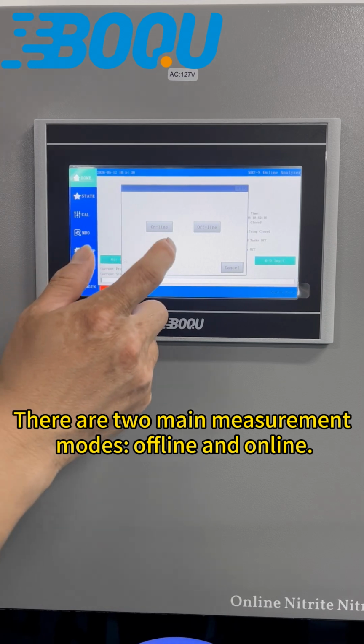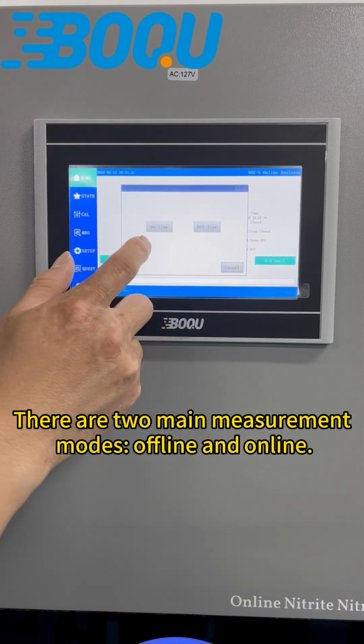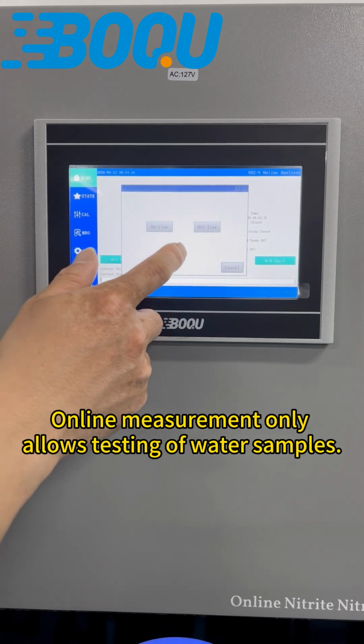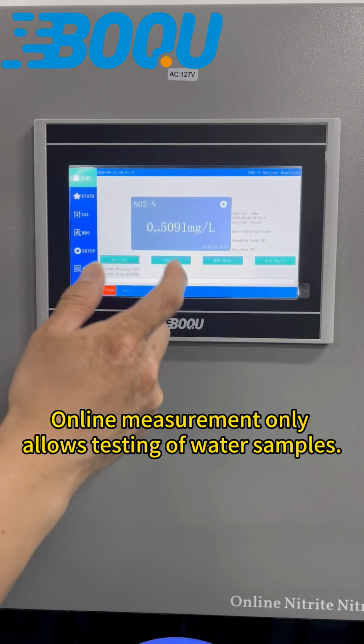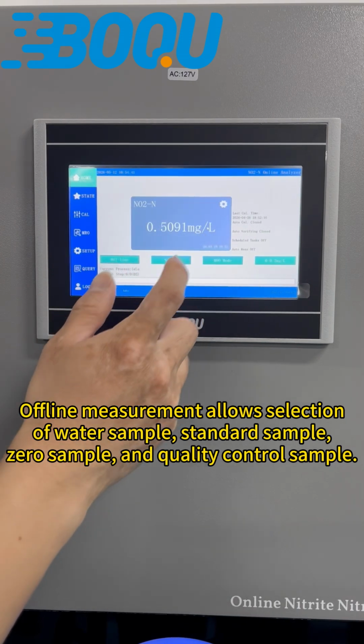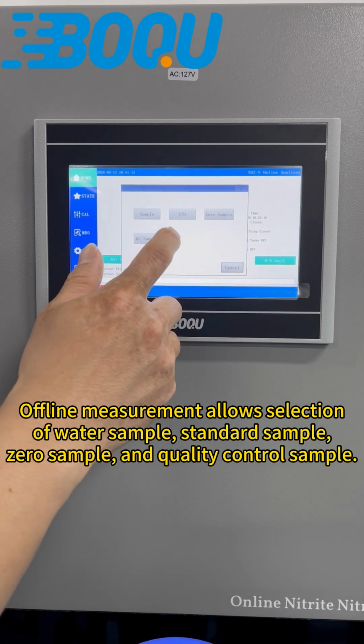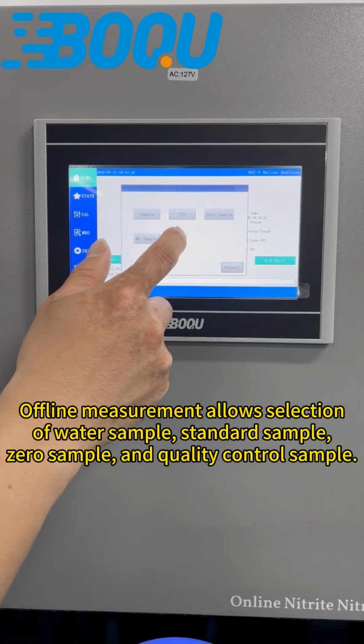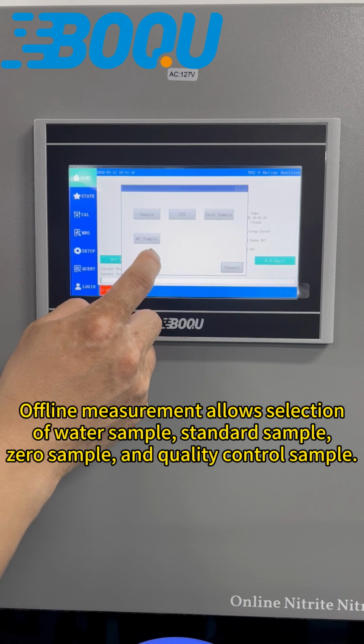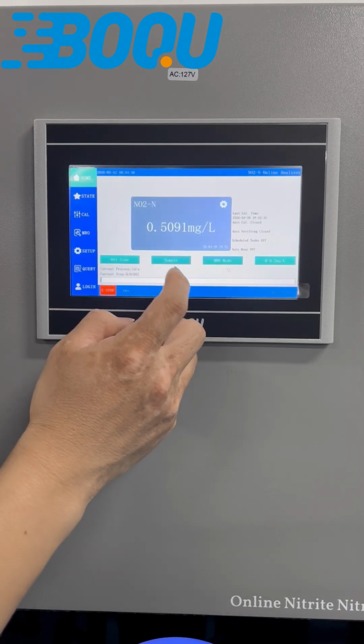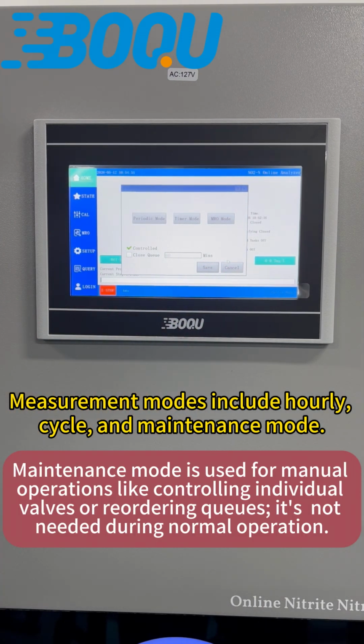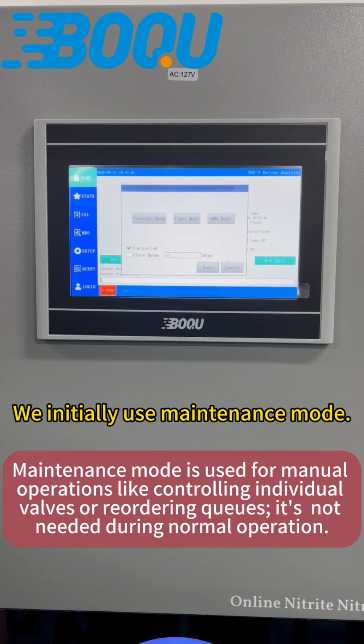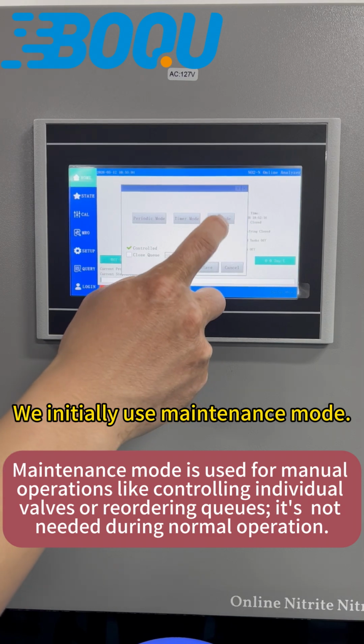There are 2 main measurement modes, offline and online. Online measurement only allows testing of water samples. Offline measurement allows selection of water sample, standard sample, zero sample, and quality control sample. Measurement modes include hourly, cycle, and maintenance mode. We initially use maintenance mode.